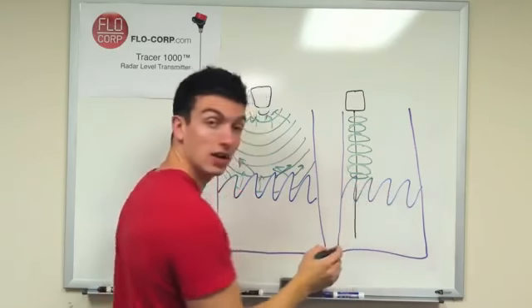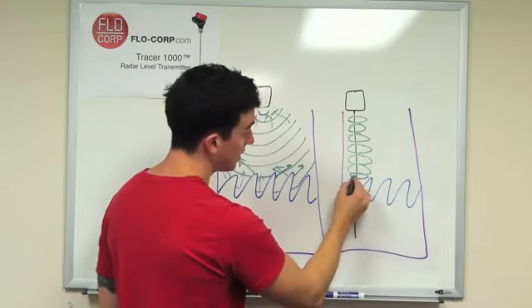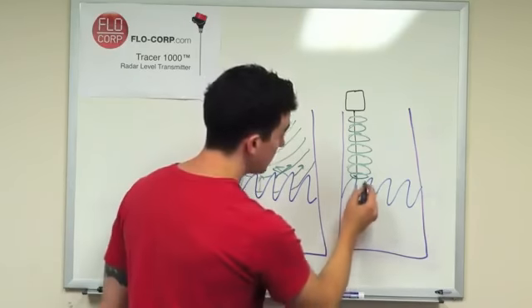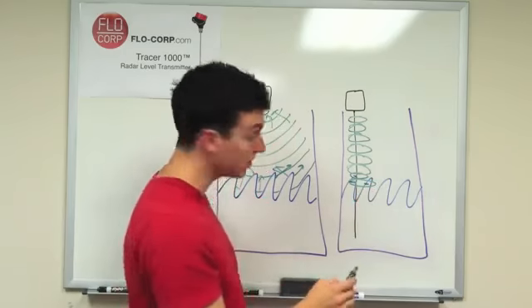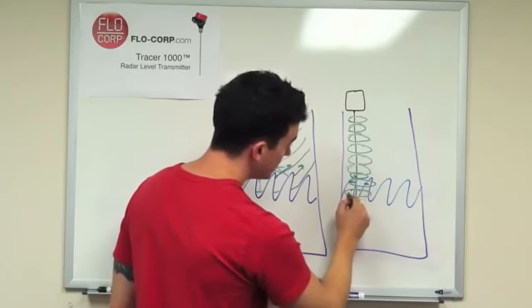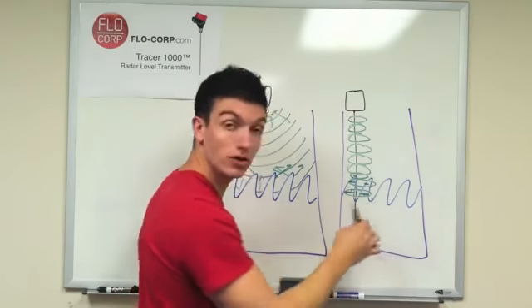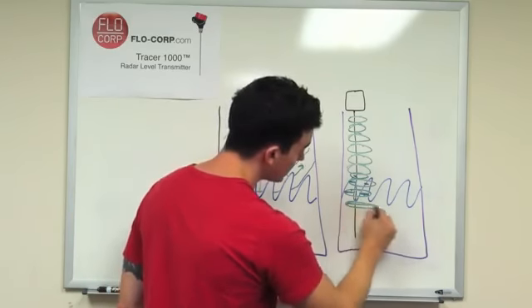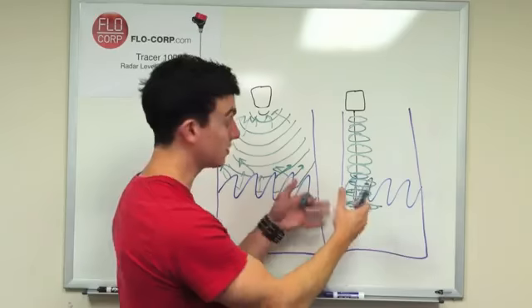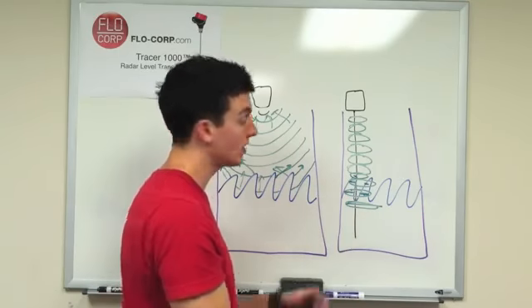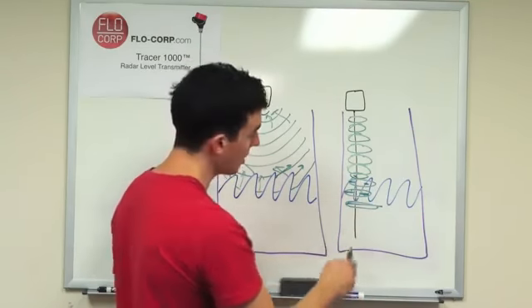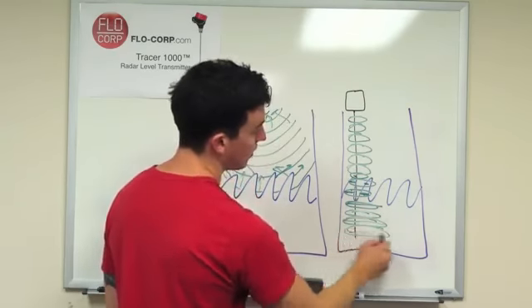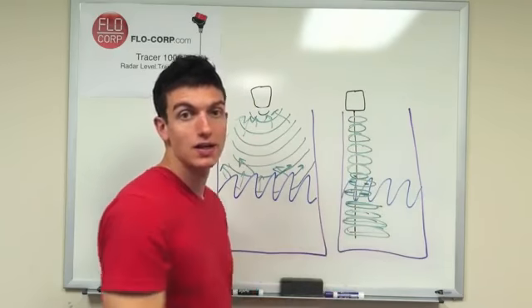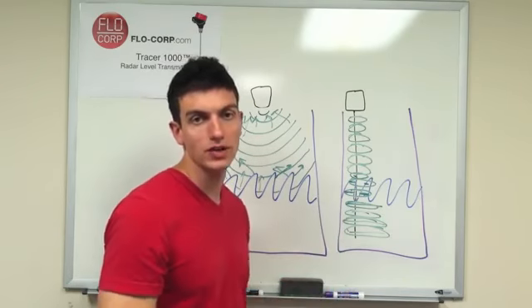okay, so when it hits here, it is going to take a measurement. It's going to say, okay, there's some liquid. It's going to realize there's some liquid here. It's going to take a measurement. Even more still. And when it gets right here, it's finally going to take the strongest signal so far. But the benefit here is it continues on to the bottom of the probe. And so it confirms, okay, that was the strongest signal. That is definitely where the level of the liquid is.